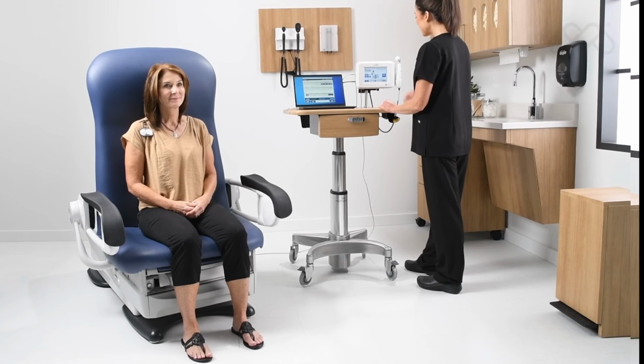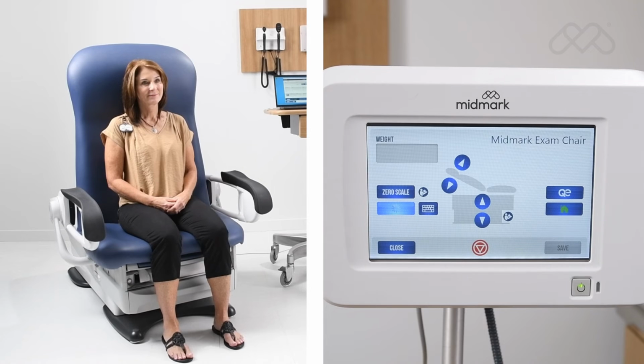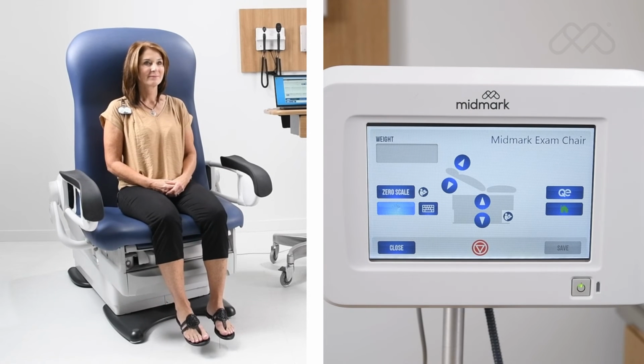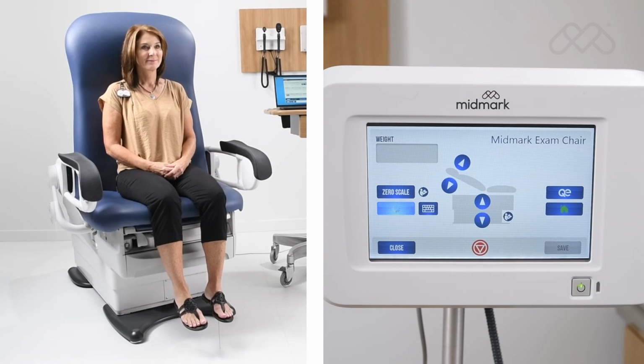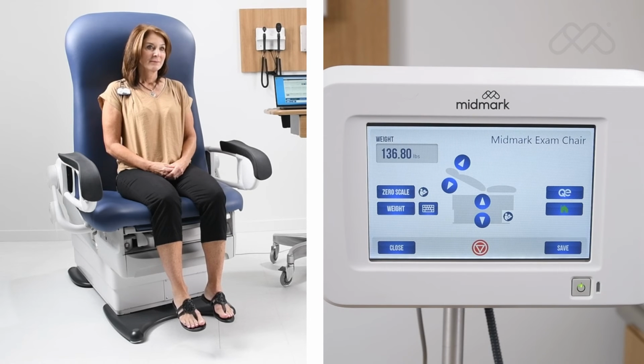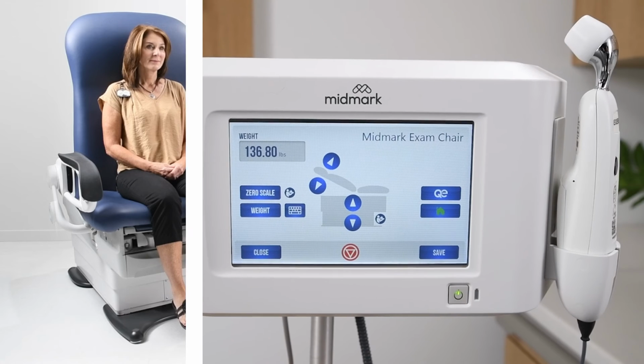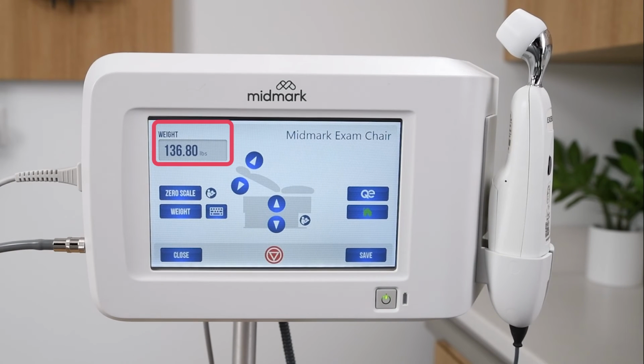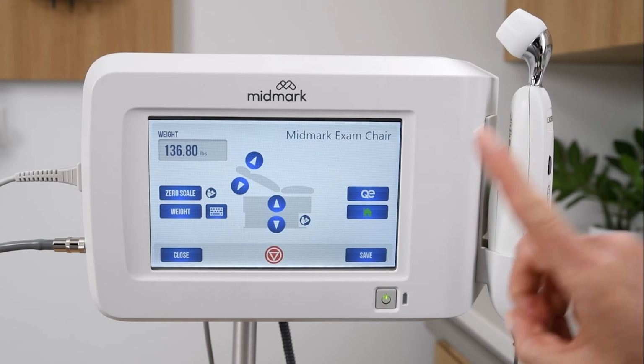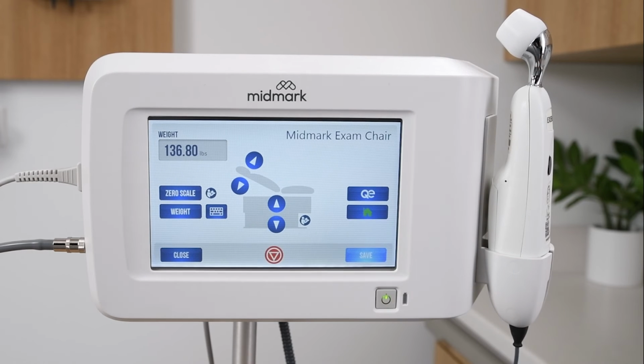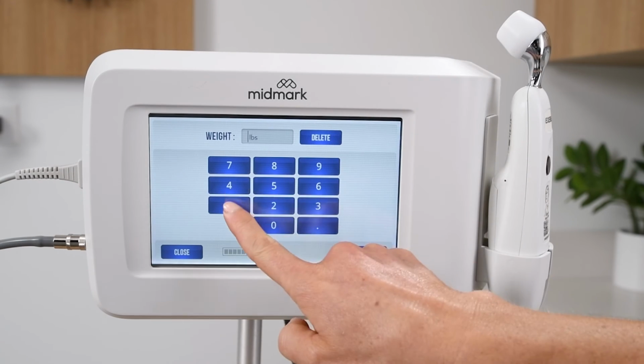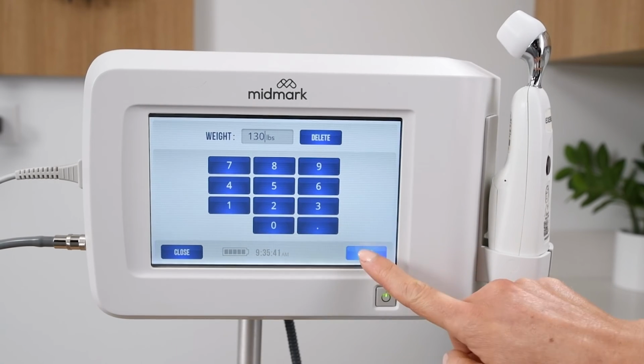When the weight button is pressed, the chair will move to ensure that the patient's feet are off the floor. The in-progress wheel will appear during weight acquisition. The weight data will appear on the screen once the weighing process is complete. Units are displayed based on the user settings in either kilograms or pounds, and 2 decimal points are shown for both kilograms and pounds. After weight acquisition, the Save button becomes active indicating the option to save the weight is available. Weight can be otherwise determined and entered manually using the keypad on the display.